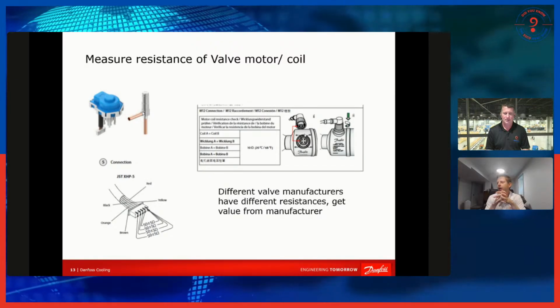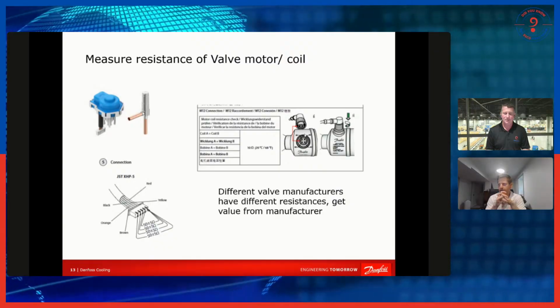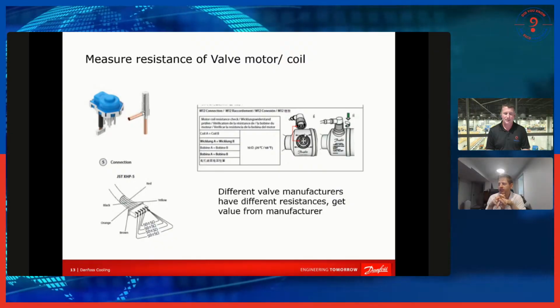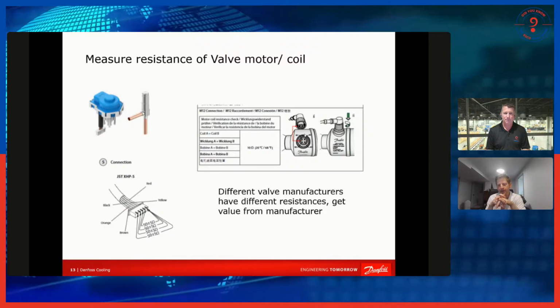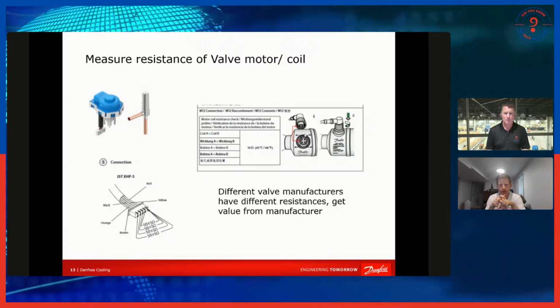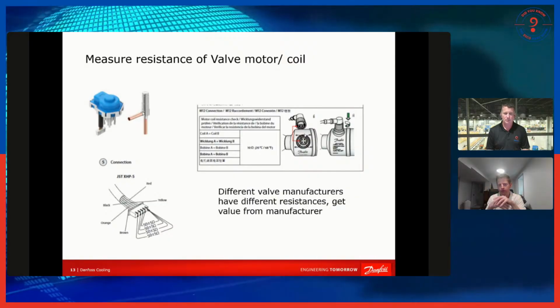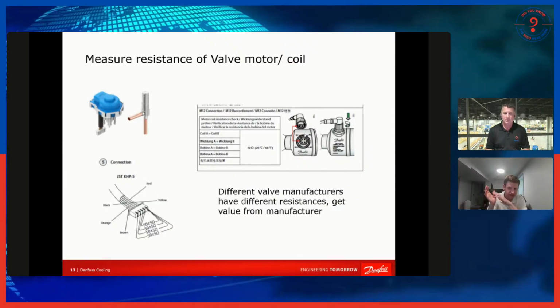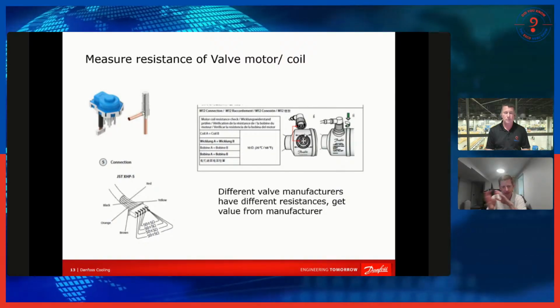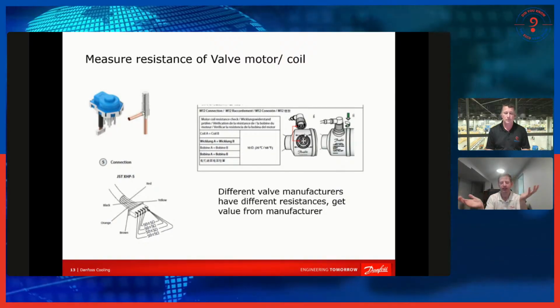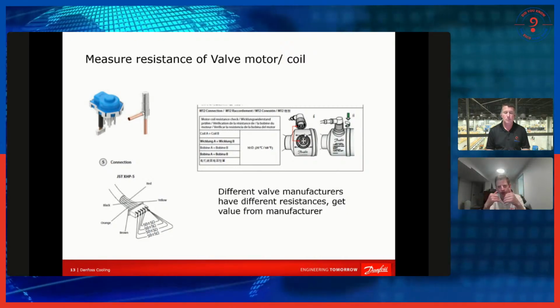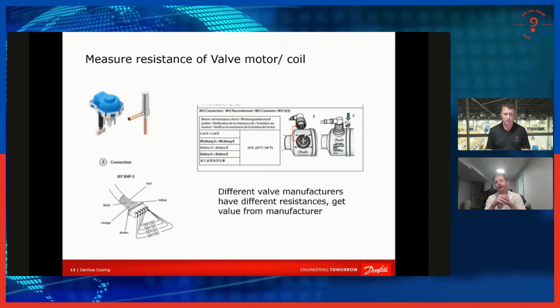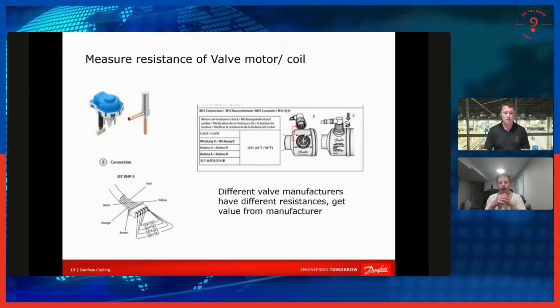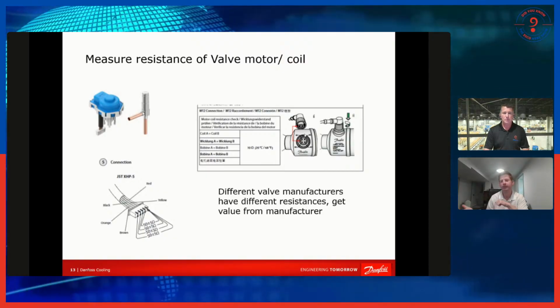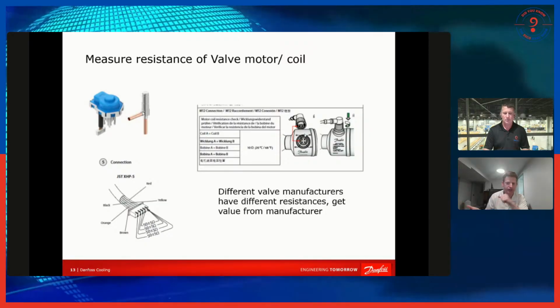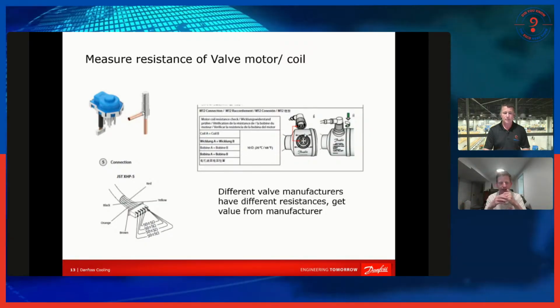So if you see open resistance, there's no continuity. What that's probably indicating to me is that one of the poles in the step motor is burned out, so it's probably not going to drive open or closed, and it's probably going to just be stuck wherever it is. And as a result, if it's stuck at 20% open, it's going to feed some. You won't shut off on low suction pressure, but you're certainly not going to do much cooling. Although depending on the situation, maybe 20% will allow you to limp along pretty well. It just kind of depends. Wherever it was when it died, that's where it's going to be.